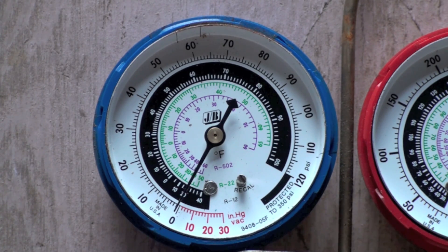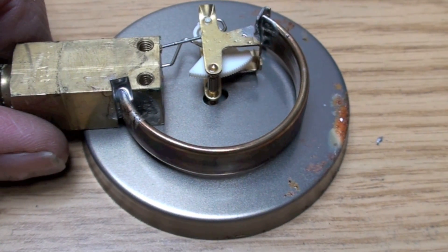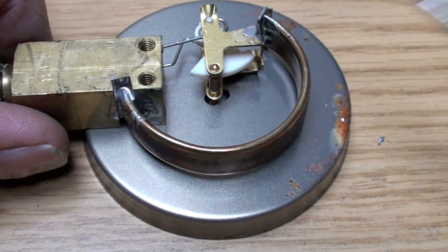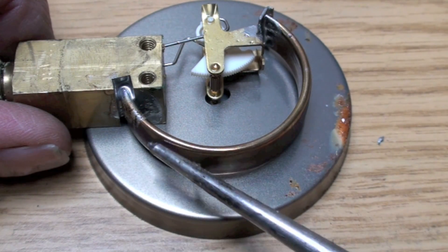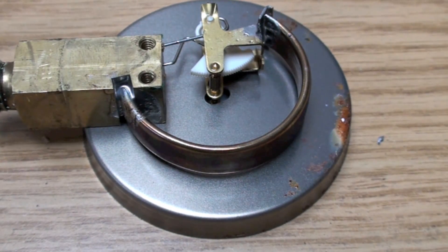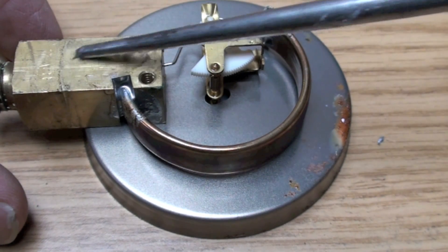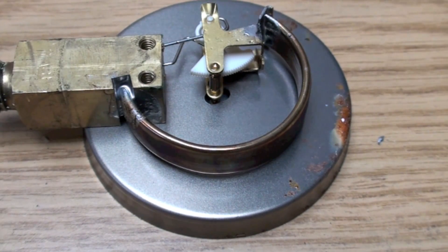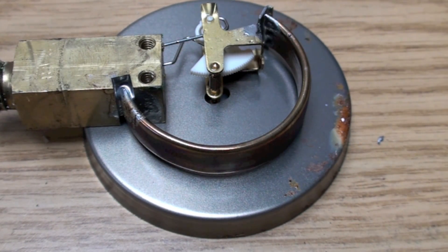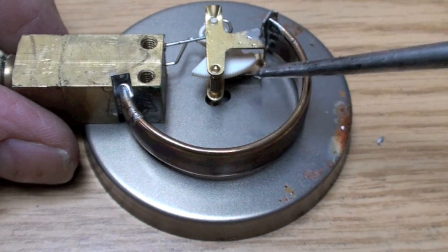Now we're showing the back side of one of these gauges. This part right here is the Bourdon tube. A Bourdon tube is kind of an interesting little device. If I put pressure on it, and the pressure comes from inside this block through this eighth inch pipe thread, if I put pressure on it it'll tend to straighten. Also, so they take advantage of this and they put a little gear right here.